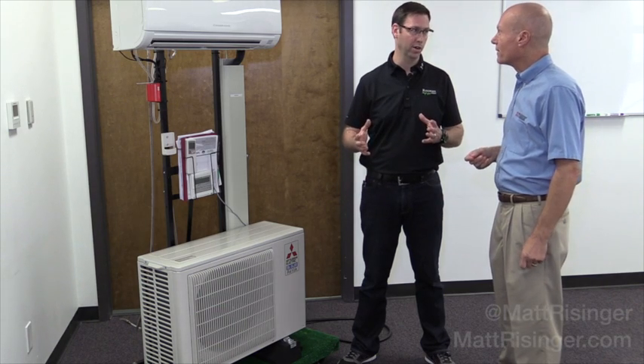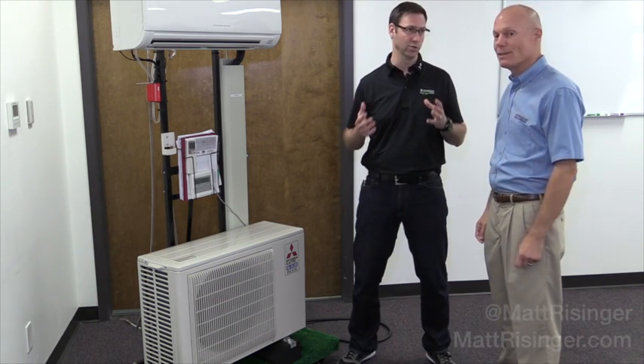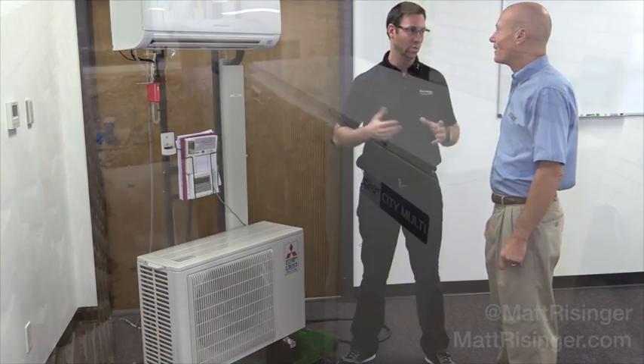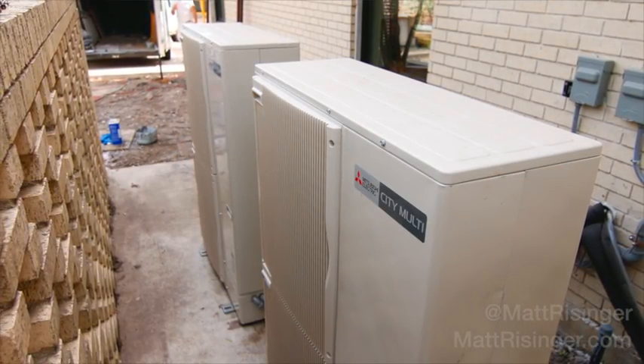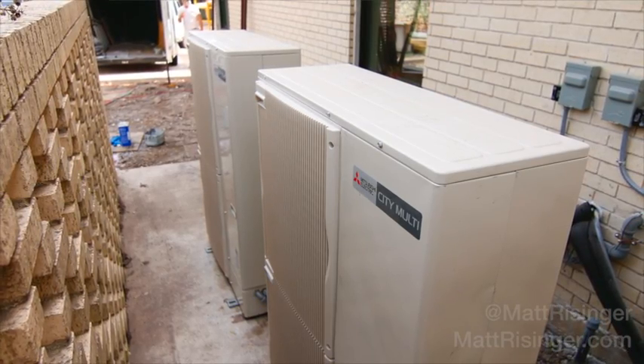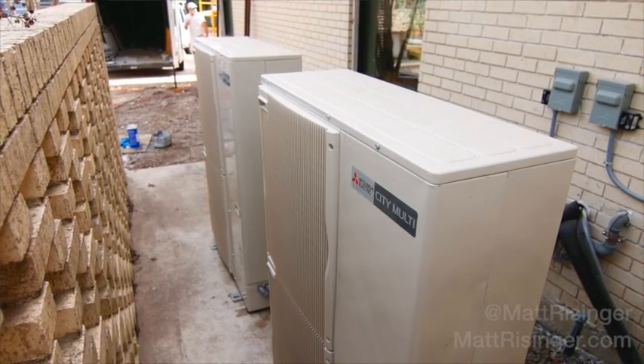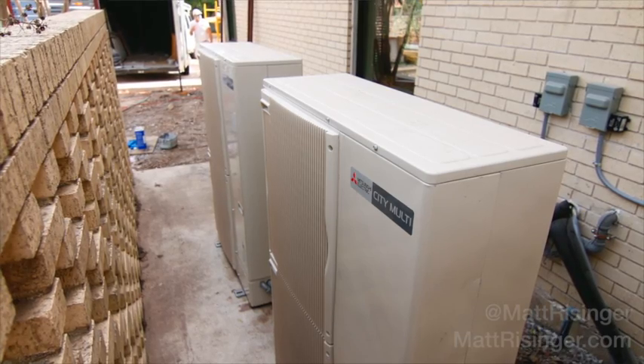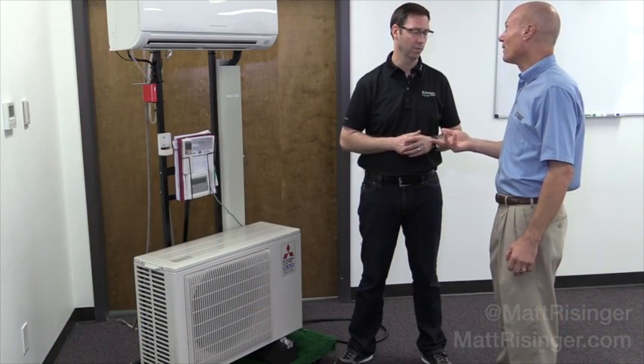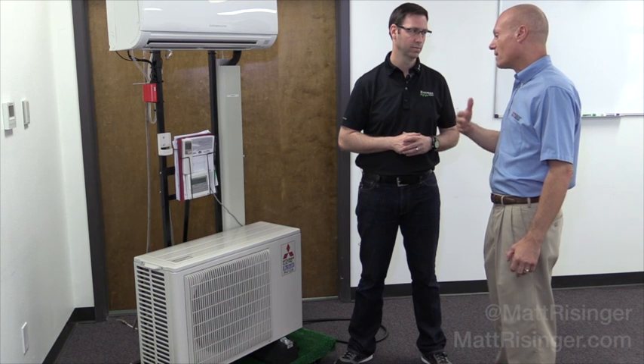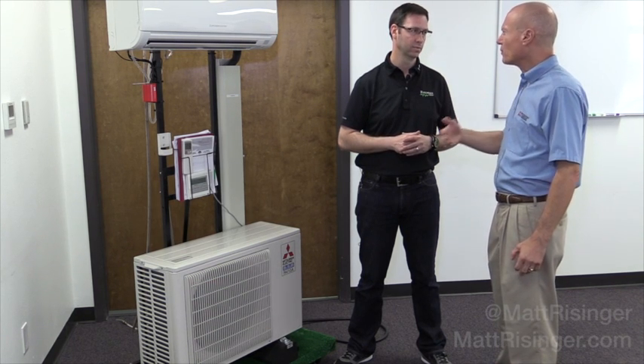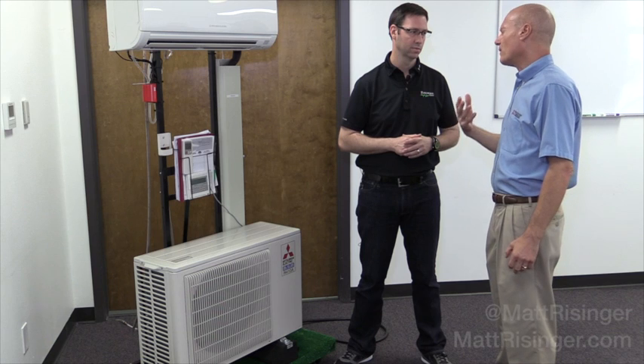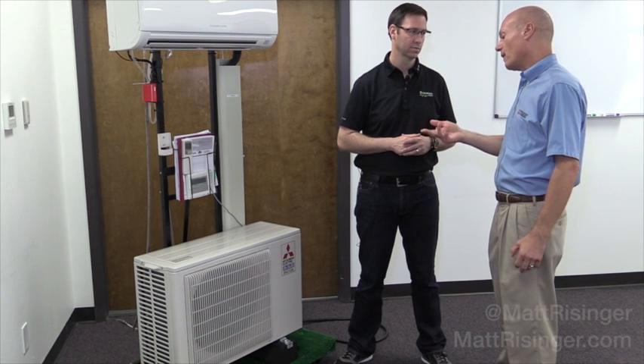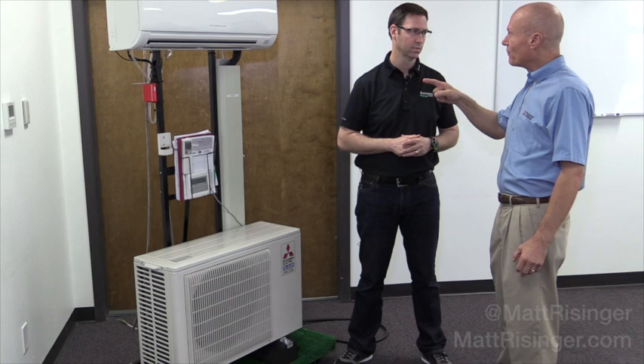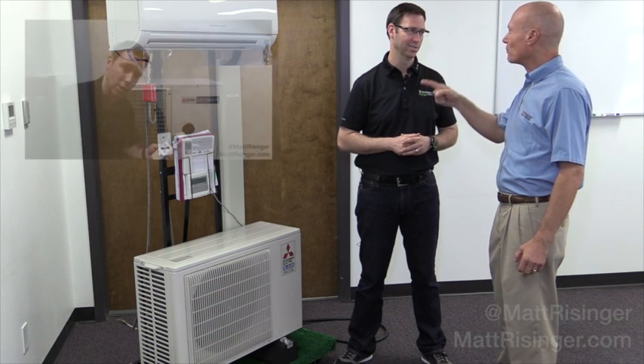We've talked about these on my blog before, referring to them as VRF, variable refrigerant flow. What's the rough capacity range on these in terms of variability? From 15% to 100%. What I always educate my customers on is that these systems almost run all the time, which is actually a good thing. They're constantly sampling air, taking humidity out, constantly moving air, but very efficient. Sometimes I'll walk outside and look at one running, and the fan is barely turning, just super slow, very efficient.